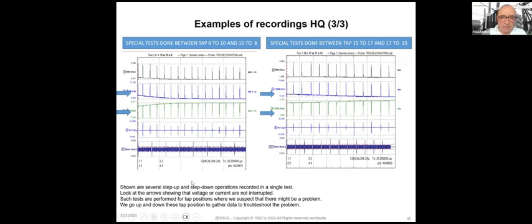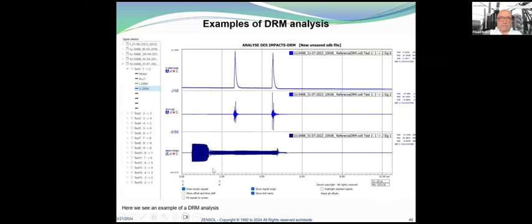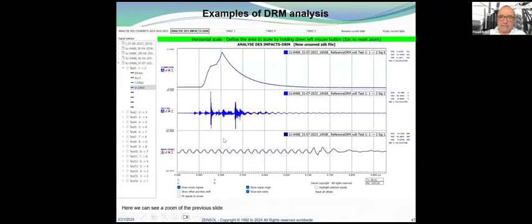Shown are several step-up and step-down operations recorded in a single test. Look at the arrows showing that voltage or current are not interrupted, and such tests are performed for tap positions where we suspect that there might be a problem. So we go up and down this tap position to gather data to troubleshoot the problem. Here we see an example of a DRM analysis, and in the next slide, we zoom in on the resistance. So after, we know exactly when the impact has occurred.